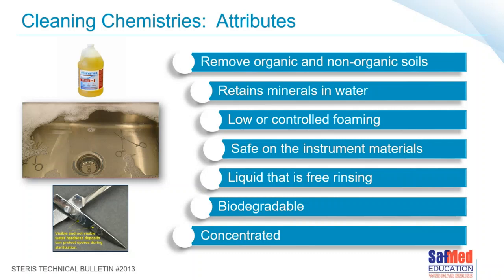We want something that is low foaming or has some form of controlled foaming, because foaming can affect your cleaning equipment. If something foams a lot in a washer disinfector, it affects the efficacy of cleaning. Proteins — which much of the patient's organic material contains — make foam. When cleaning manually, if there's less foam in the basin, you can see more clearly what's happening, and hopefully you don't injure yourself with a skin hook or piece of equipment you're trying to clean.